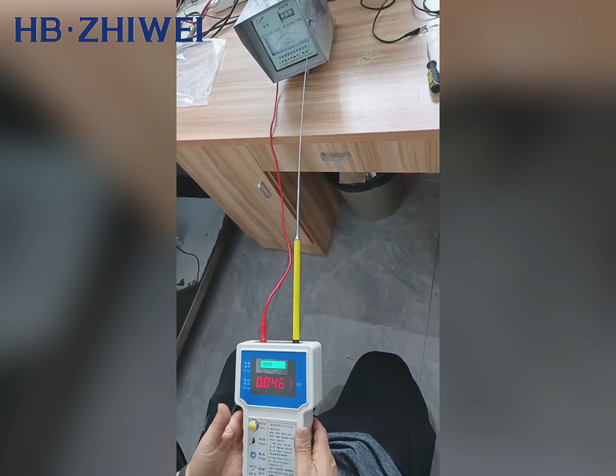The test is over. Here is a special reminder for you. During the test, the telescopic rod must be in perfect contact with the product being tested, otherwise sparks will be generated. This will ensure the safety of the test during the test. Lightning arrestor counter tester. Overall introduction completed.